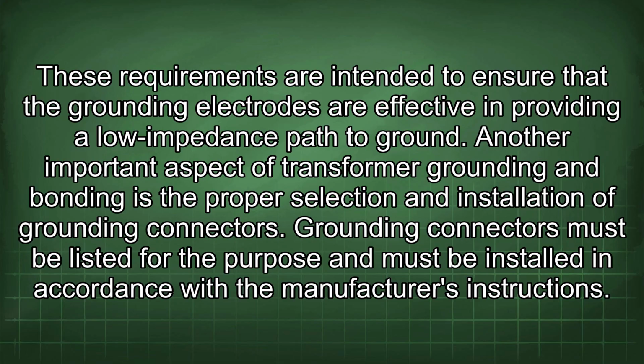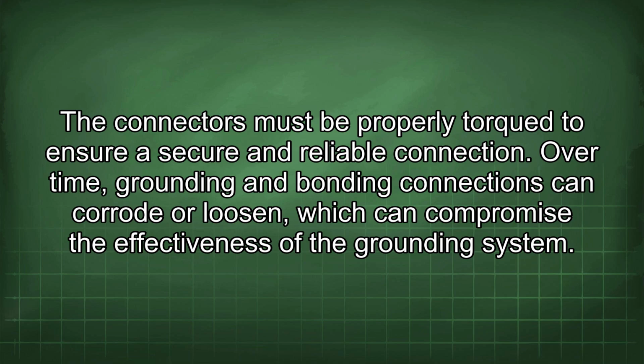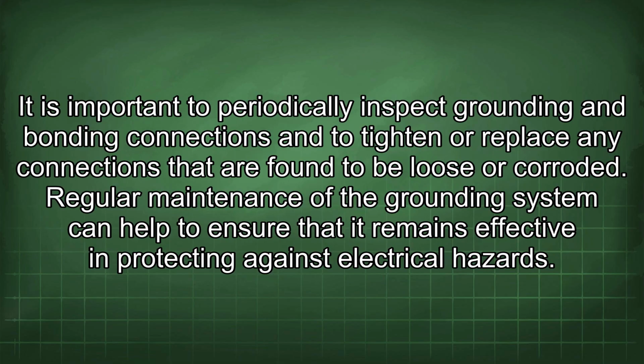Another important aspect of transformer grounding and bonding is the proper selection and installation of grounding connectors. Grounding connectors must be listed for the purpose and must be installed in accordance with the manufacturer's instructions. The connectors must be properly torqued to ensure a secure and reliable connection. Over time, grounding and bonding connections can corrode or loosen, which can compromise the effectiveness of the grounding system. It is important to periodically inspect grounding and bonding connections and to tighten or replace any connections that are found to be loose or corroded. Regular maintenance of the grounding system can help to ensure that it remains effective in protecting against electrical hazards.